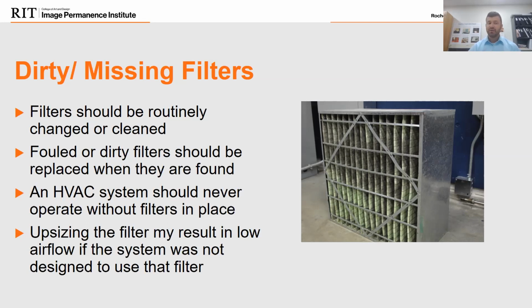And as I discussed earlier, upsizing a filter, if you're using a MERV 8 and ASHRAE is recommending a MERV 14 for COVID safety reasons, with most units it's not just plug and play. You can't just pull a MERV 8 out and put a 14 in. As you go up on the MERV scale, the more you impede the airflow. And if your system was not designed to compensate for that, you can put some strain on your systems, which could damage some components.